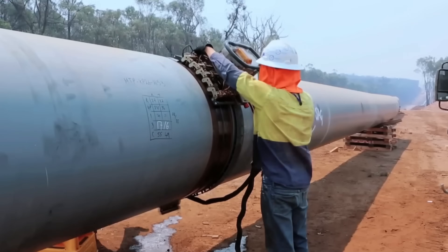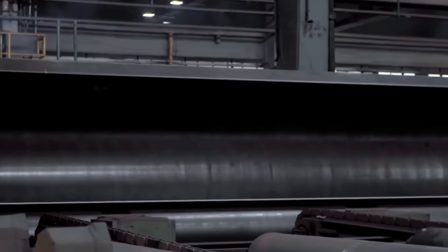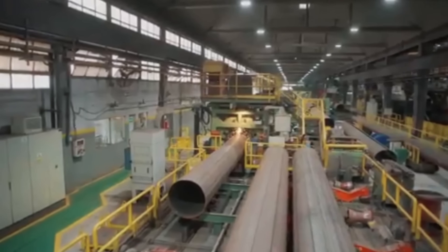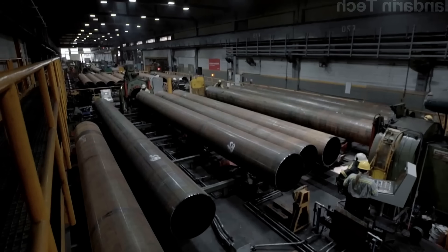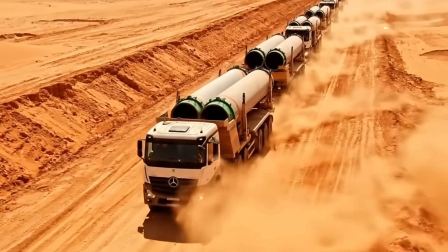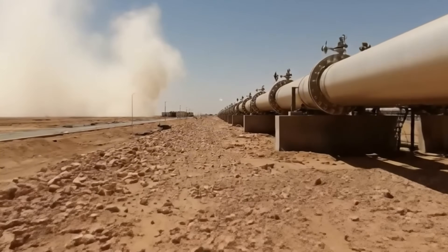High-strength carbon steel forms the backbone of the system. Rectangular steel plates are cut to precise dimensions, then fed through multi-axis rolling machines where they gradually bend until the edges meet. Each section measures about 12 metres long with walls nearly 25 millimetres thick. Automated welding systems complete up to 150 joints per day on large-diameter transmission pipes. Every joint undergoes automated ultrasonic inspection before workers apply a multi-component liquid epoxy coating. Construction crews prepare corridors approximately 40 metres wide, advancing at 1.5 kilometres per day.